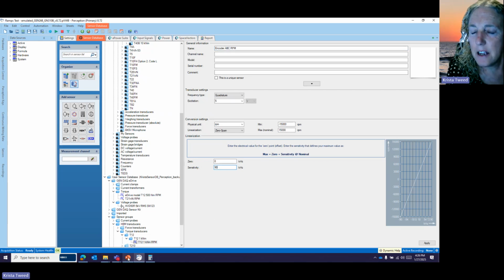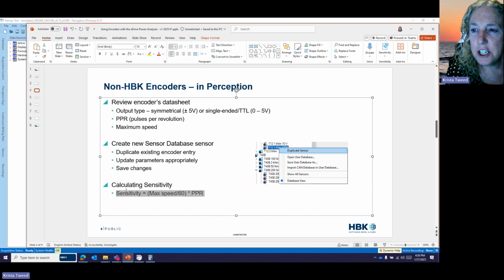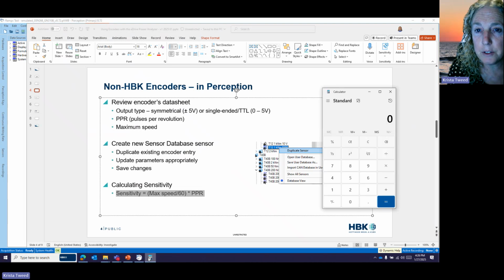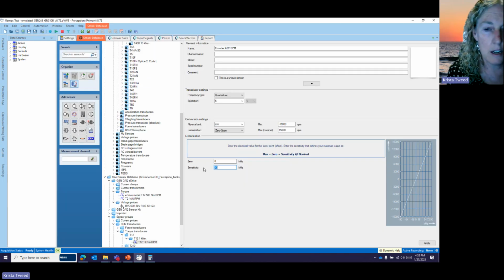How do I do that? The equation to determine your sensitivity is to take your maximum speed in RPM, divide it by 60 to convert it to hertz, and then multiply by the pulses per revolution. So in my example, I have a 15,000 RPM sensor. I'm going to divide that by 60, and it has 2048 pulses per revolution. So that tells me my sensitivity is 512 kilohertz. So I'm going to go back to Perception, enter 512. You can see the units are kilohertz, and I'm going to apply.